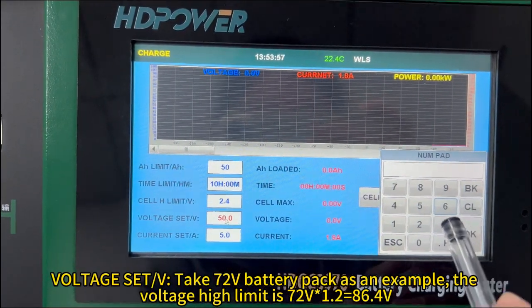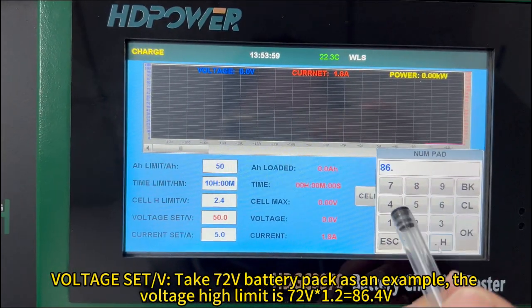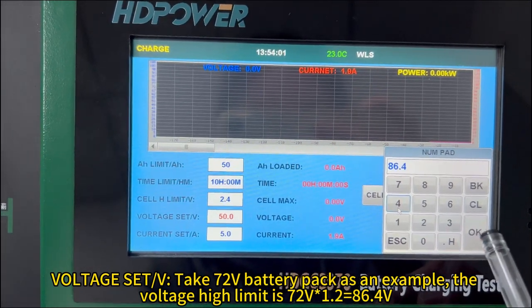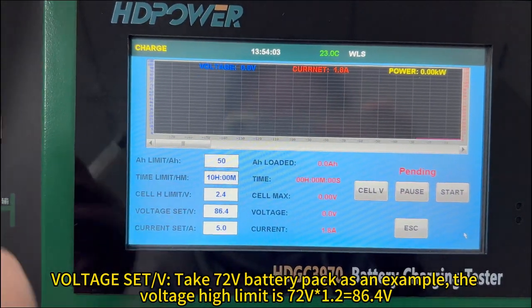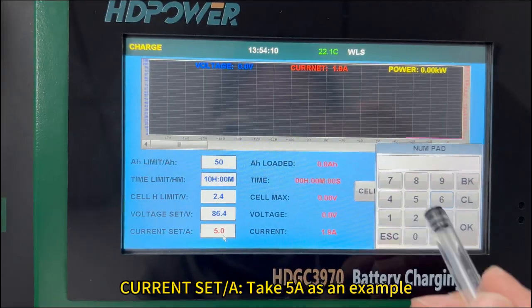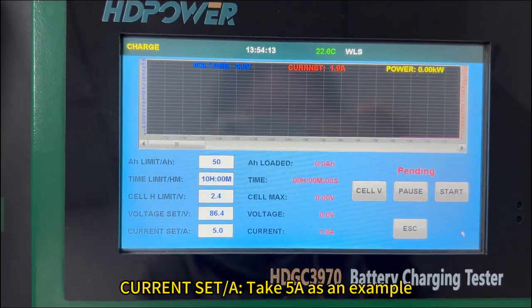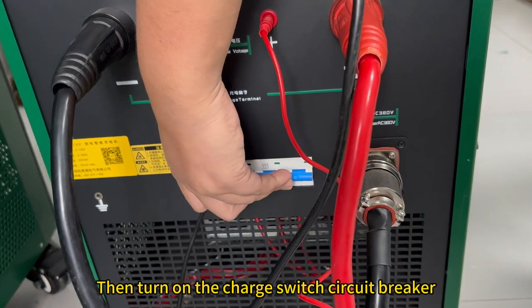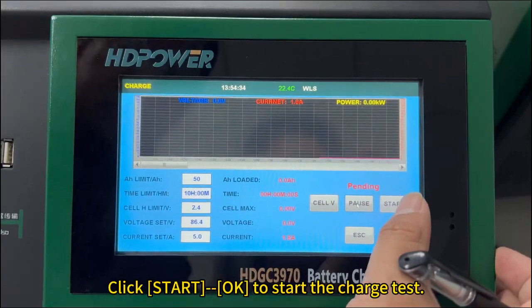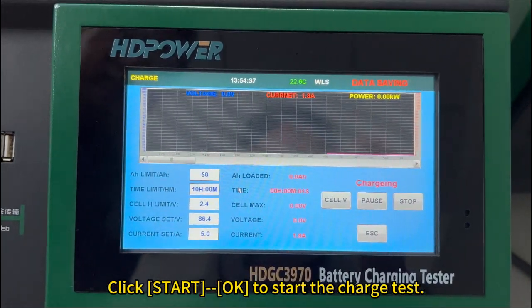Voltage set, V, take a 72 volt battery pack as an example. The voltage high limit is 72 times 1.2 equals 86.4 volts. Current set, take 5A as an example. Then turn on the charge switch circuit breaker. Click Start, OK to start the charge test.